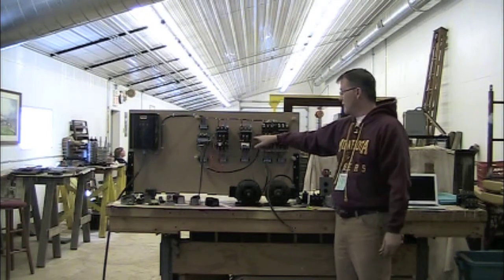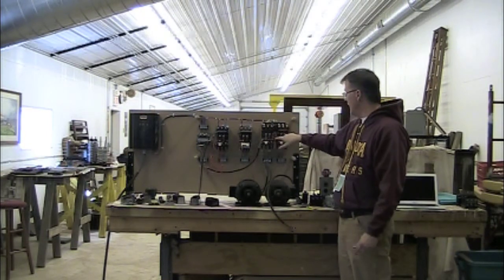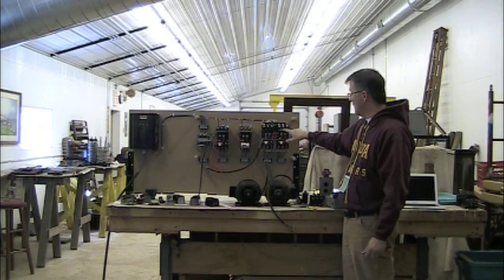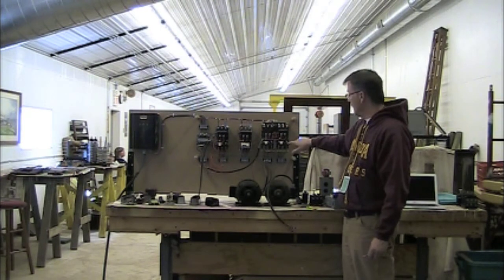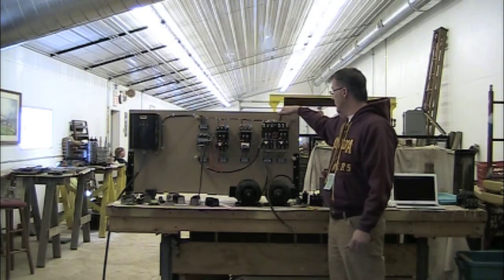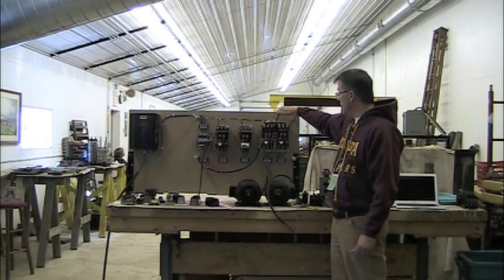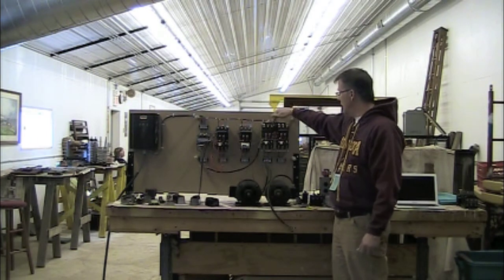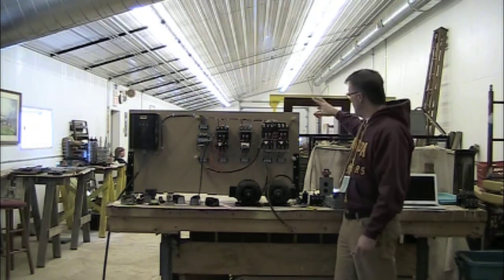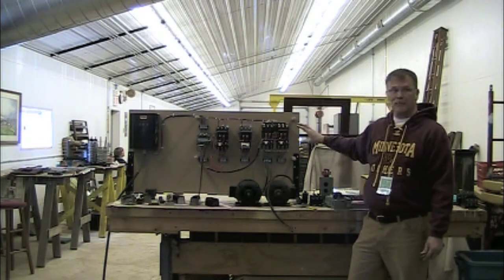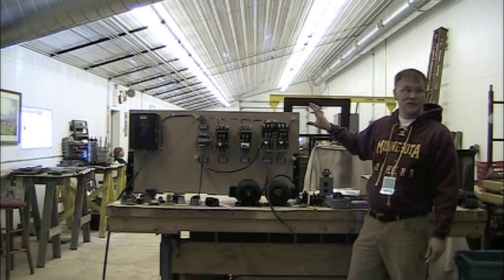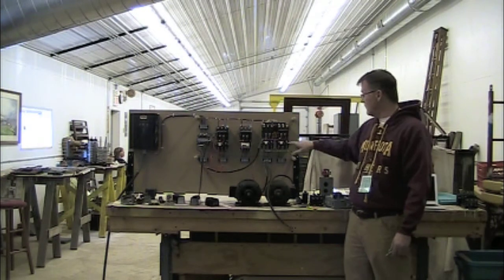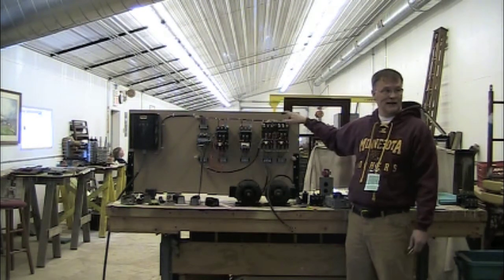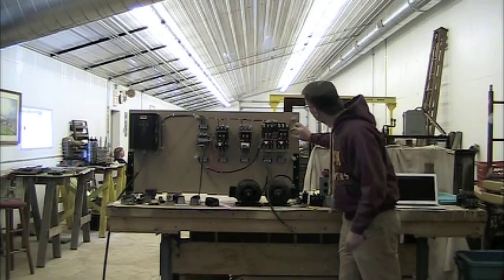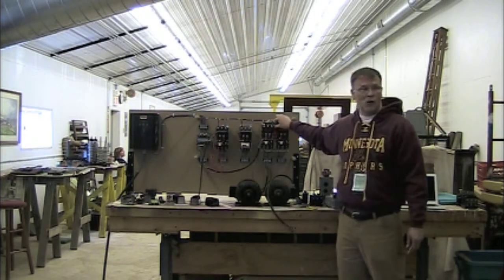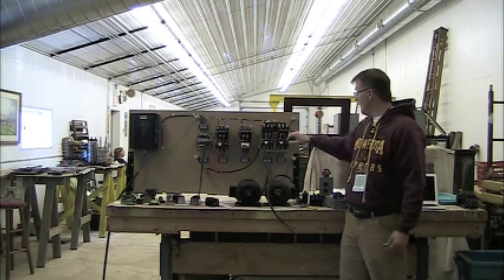So like I said, this is all based on the same Bulletin 500 contactors, the 596 overload, or auxiliary relays, the overload blocks. It's got the jumpers between here that's connecting L1 to L1, L2 to L2, L3 to L3. This is a separate winding 2-speed controller. So it's actually the simplest there is, because all you're doing is going through one contactor or the other. The other piece that's in here is there's a little coordinator in here. So there's a mechanical interlock.